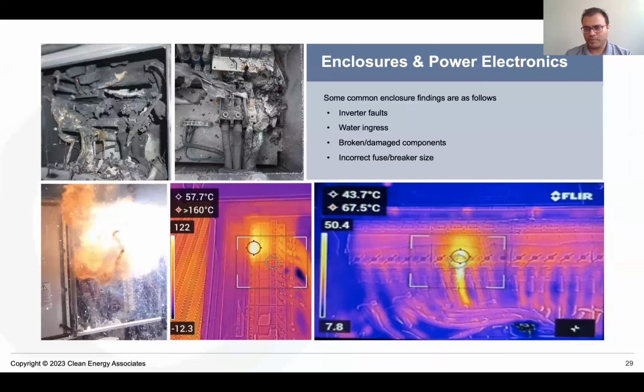My choice would be to open each enclosure at your site, open inverters, open DC combiner boxes, open AC switchboards, open AC combiner panels, and inspect them. That is how I'm going to invest my 3 hours on your site. Most of the thermal events that I have participated in the investigation, not direct investigation, but supporting the investigation, the issue has originated from the enclosure. And we have inverter faults that go unnoticed. We have water getting inside the enclosures due to bad gaskets or the conduits or the drill holes that are not fixed. We have broken or damaged components inside the inverters that are not fixed. We have incorrect fuse sizes and breaker sizes that can lead to these thermal events.